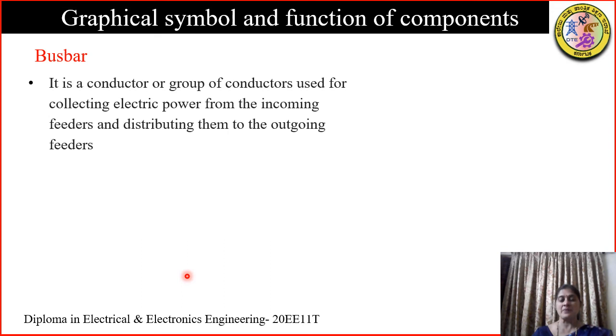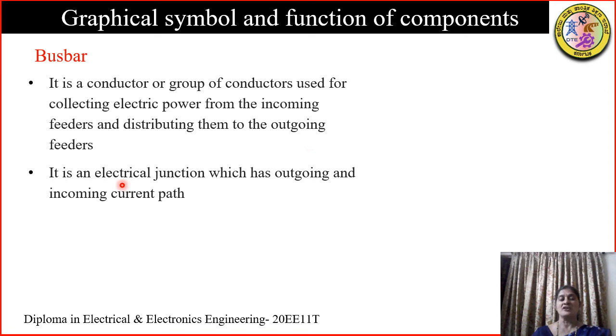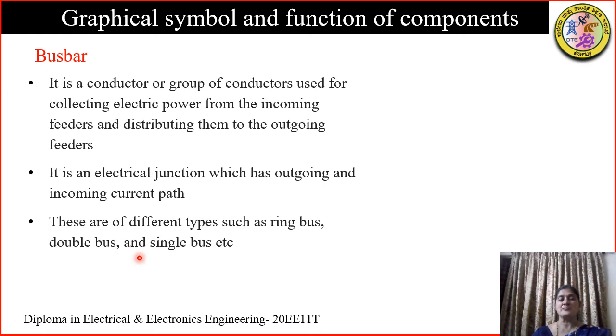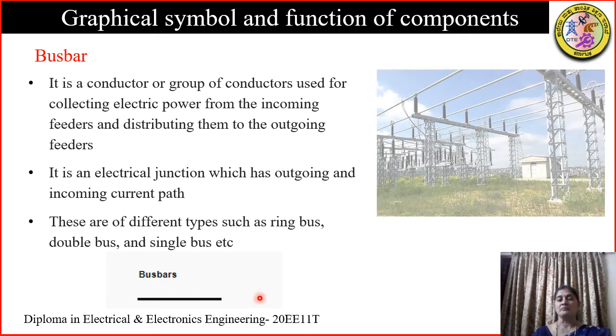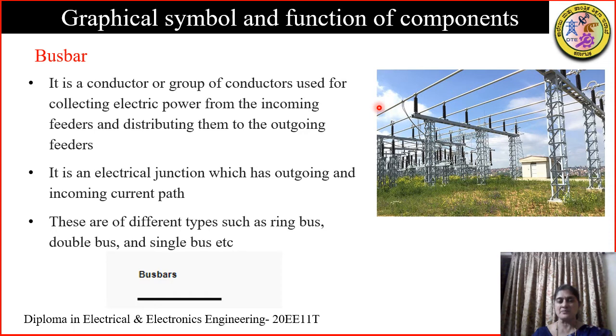The next component is the bus bar. A bus bar is a conductor used for collecting power. Every substation will have incoming lines and outgoing lines, and the bus bar provides an electrical junction for outgoing and incoming current paths. There are different types of bus bar connections depending upon the level of reliability required, including ring bars, double bars, and single bars. The bus bar is shown by a single thick line in diagrams.